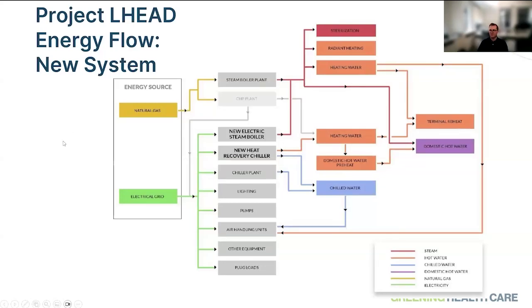So Robert earlier was mentioning syncing up simultaneous heating and cooling loads, and that's the job of the heat recovery chiller. In this case, we were sizing a heat recovery chiller not for the summer cooling load, which is thousands of tons, but for the summer heating load, which was around 4 million BTUs, requiring about 200 to 250 tons of cooling input. So that was the starting point for the heat recovery chiller.